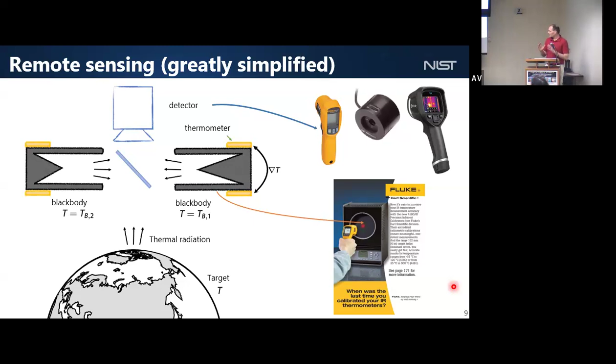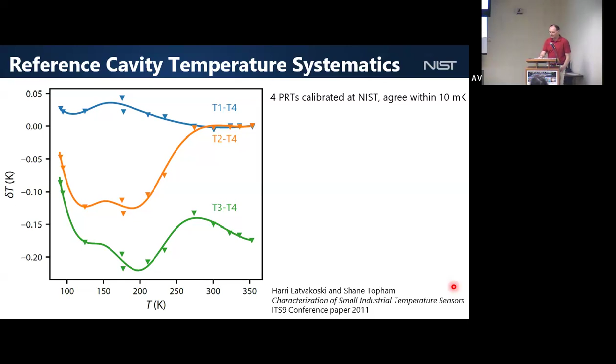But things sometimes go wrong. This is a story that you can glean from this conference proceedings paper listed here at the bottom. There's a group at the Space Dynamics Laboratory that sent 4 platinum resistance thermometers to NIST to be calibrated. And so NIST calibrated these thermometers. They agreed within 10 millikelvin. And we shipped them back to Utah, and then they get mounted onto their reference black body, and then they measure. Do they agree? And they don't.